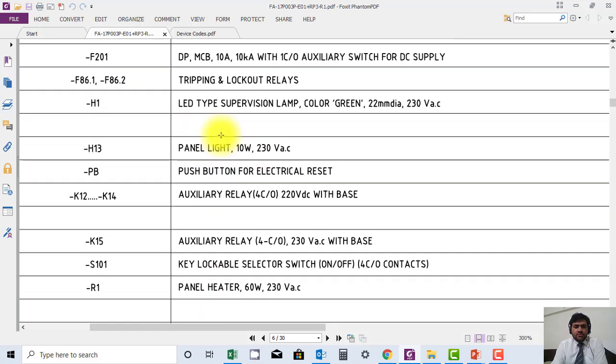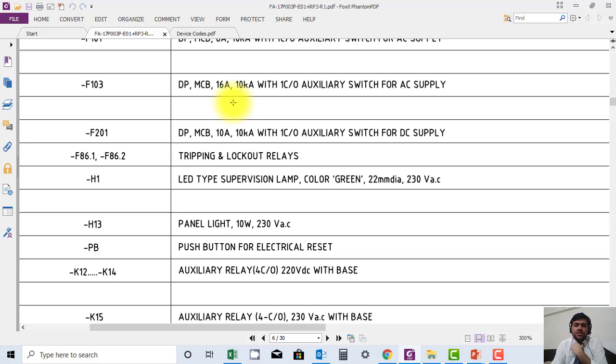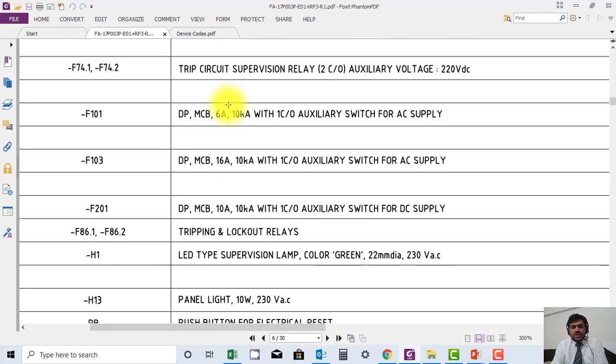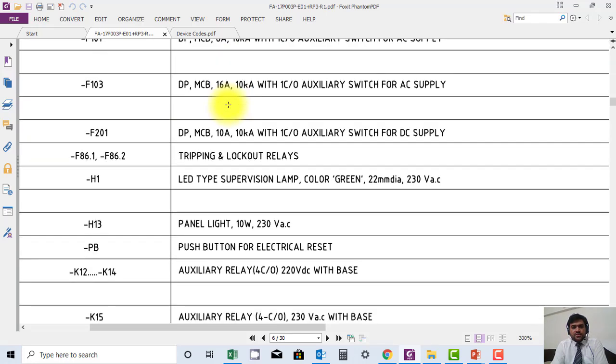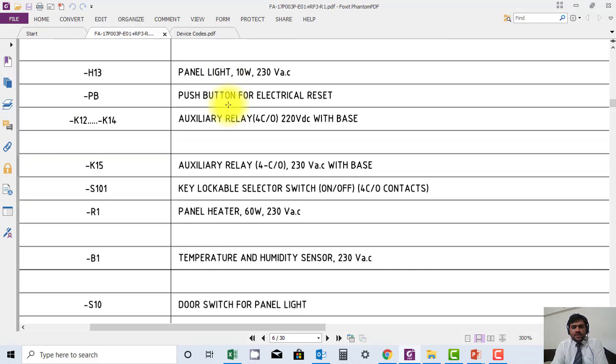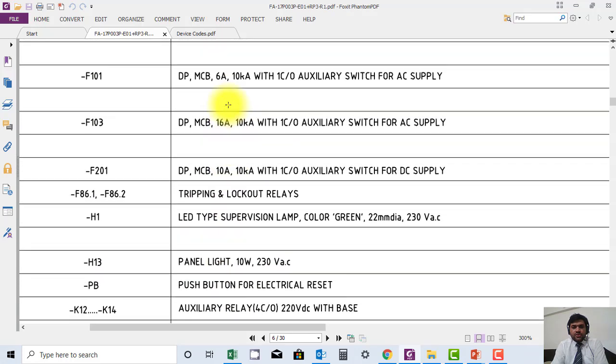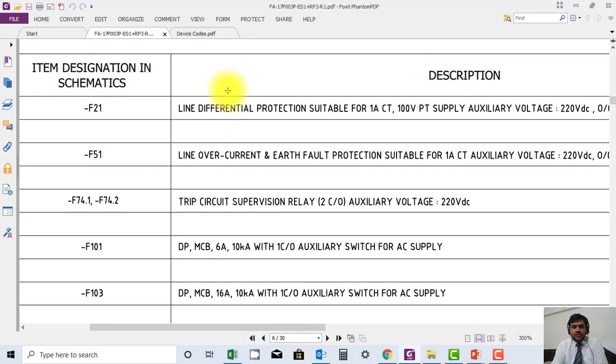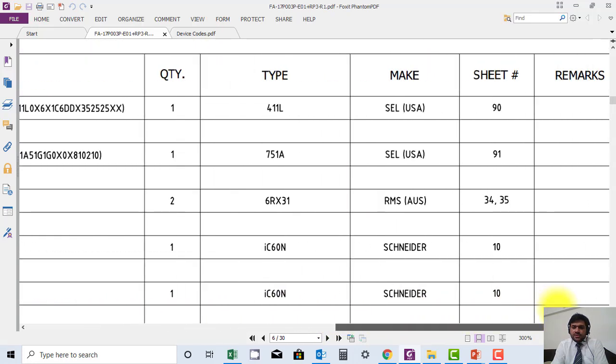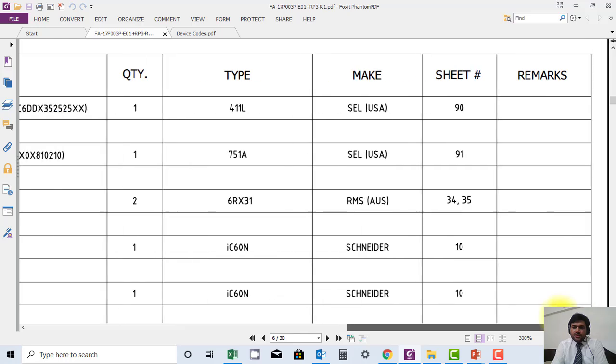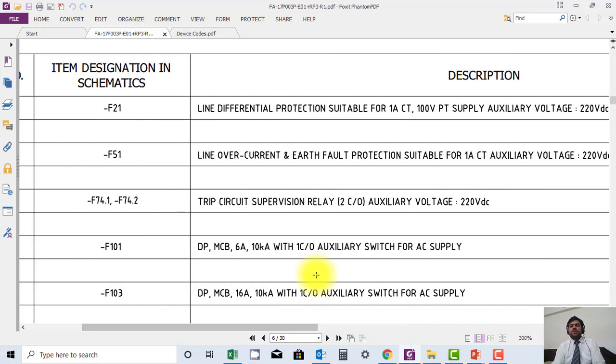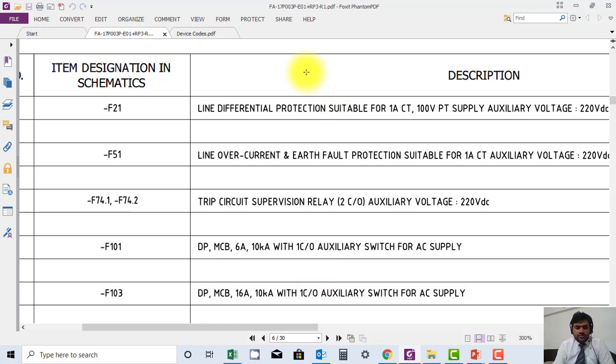If the information on the relay is already gone, like the label is burned, you can open the drawing and open this sheet list of apparatus and you can find the ordering code. If you are doing design review, you have to make sure that the ordering code should be mentioned correctly here. In case during maintenance you want to order equipment, you should know the ordering code. This is very important for maintenance and testing point of view. Thank you.